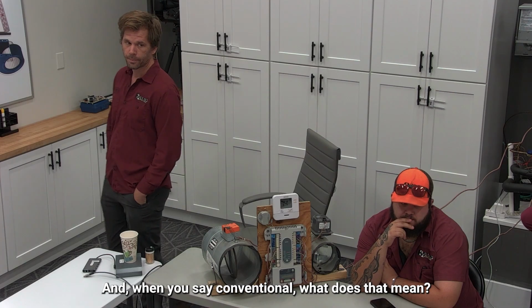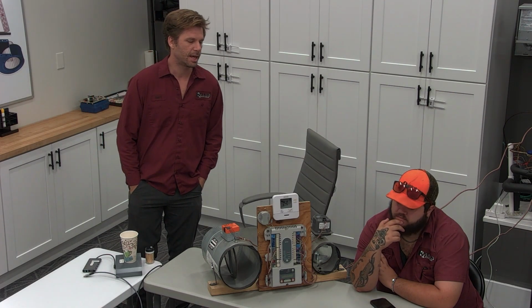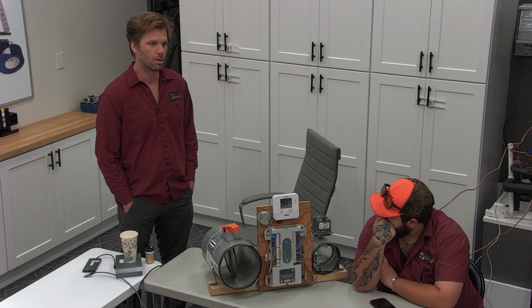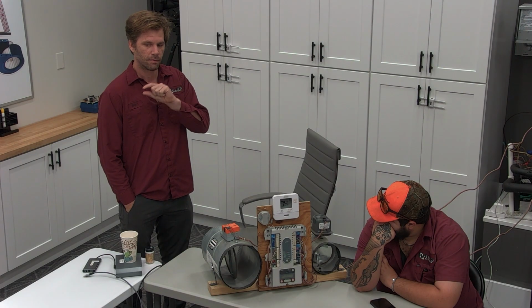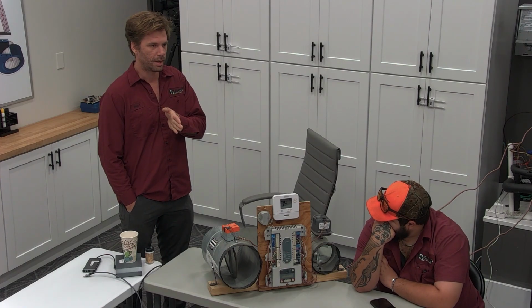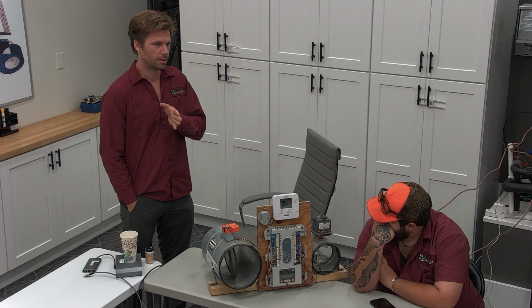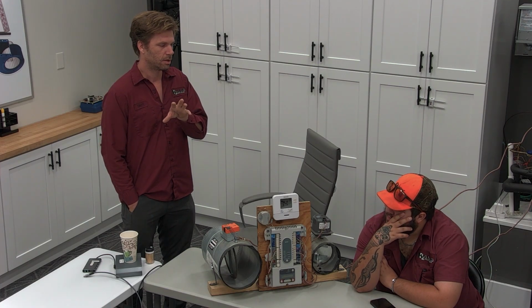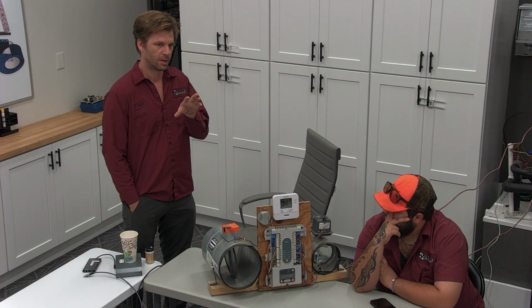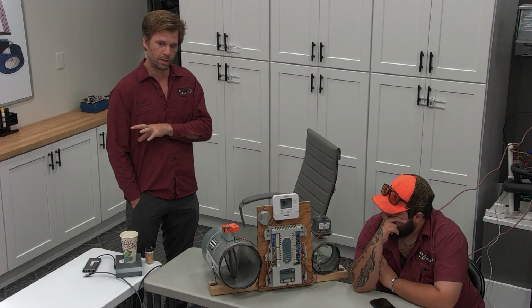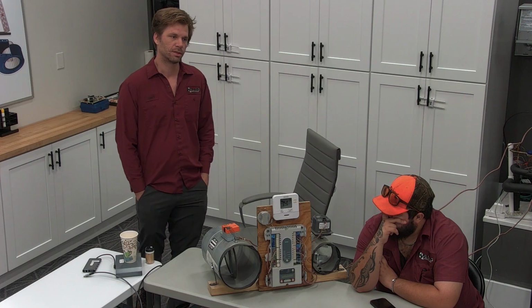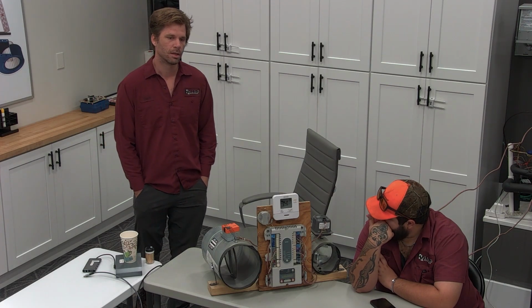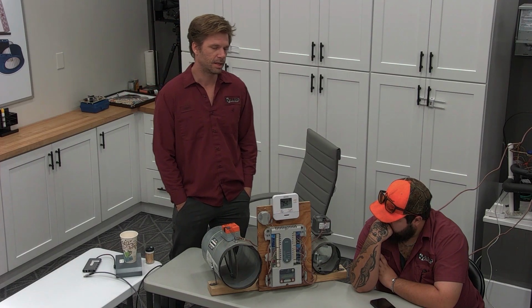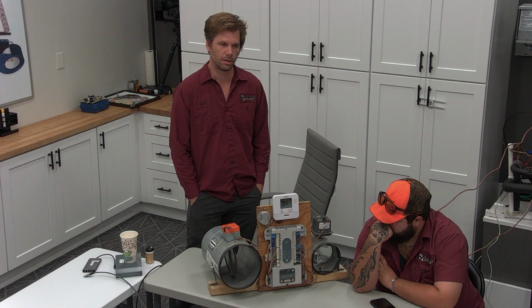And when you say conventional, what does that mean? Okay, so conventional means a thermostat that is not going to be using an O wire. It's just controlling heat with the Y call or with the W call, and cool with the Y call. A conventional system, when it calls heat, doesn't energize Y. It's not calling a condenser. It's only energizing W. And so conventional traditionally is for a furnace system, or a straight cool where you would have only electric heat would be a conventional setup. So you don't want your condenser calling if it's not a heat pump in heat mode, right? Because then you would be running your heat and your cool together.